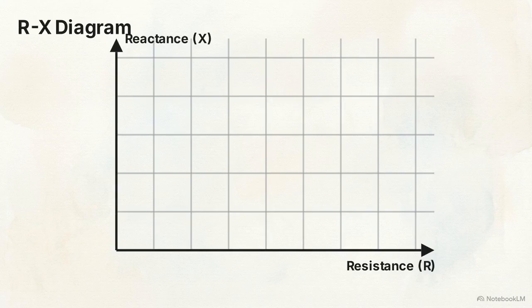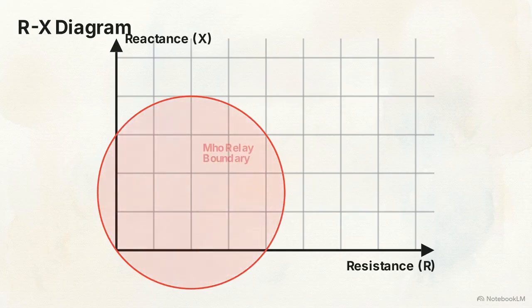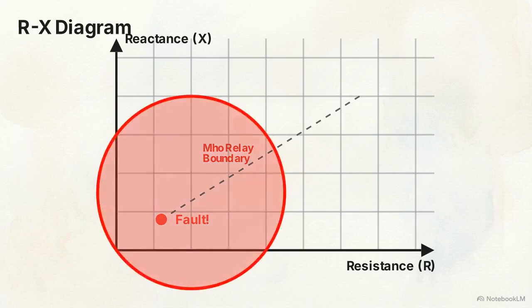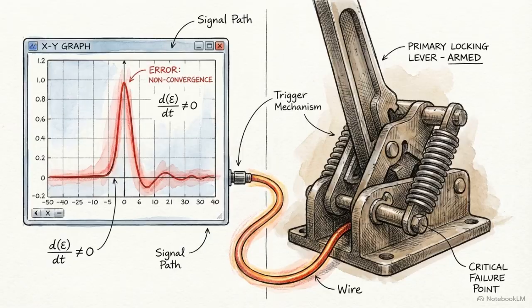A specific type of distance monitor, called a Mho relay, draws a circular boundary on this map. As long as the power grid is healthy, the math plots safely outside the circle. But if a tree falls on the power line, the math changes and plots a new point. If that point lands inside that boundary, the relay knows there is a problem and triggers a trip. The relay's job is purely informational. Once it mathematically proves a fault is happening, it passes the heavy lifting to the brawn.